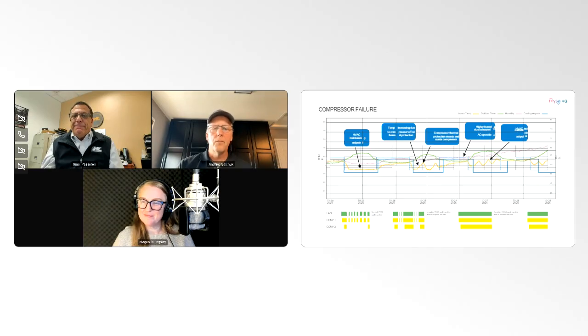And I think if you're monitoring thermostat set points with an EMS platform, you might see that the system itself is working perfectly fine for some time, but all of a sudden, a couple of months into the heating season, systems are running 12, 14, 18 hours a day. This is typically when a failure is going to happen: systems under stress or just constantly running. So as much as preventive maintenance can help, you still can't control or determine when components are going to fail.